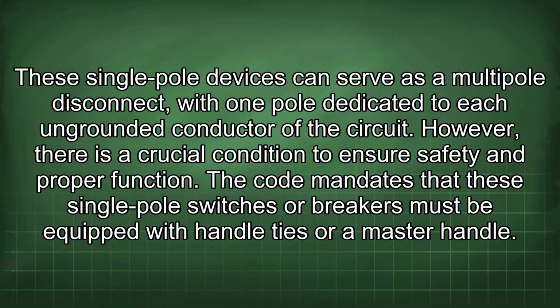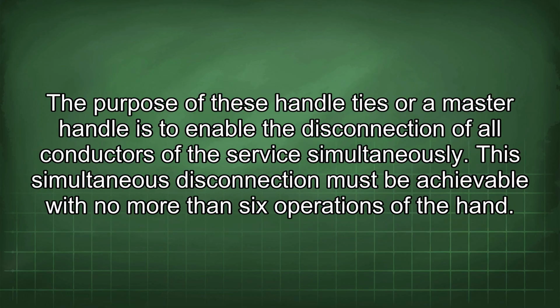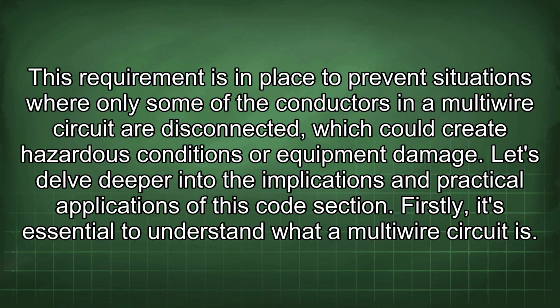The code mandates that these single-pole switches or breakers must be equipped with handle ties or a master handle. The purpose of these handle ties or a master handle is to enable the disconnection of all conductors of the service simultaneously. This simultaneous disconnection must be achievable with no more than six operations of the hand. This requirement is in place to prevent situations where only some of the conductors in a multi-wire circuit are disconnected, which could create hazardous conditions or equipment damage.